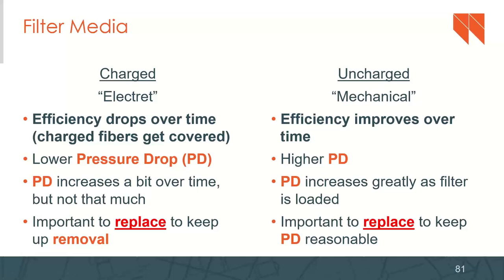With both of these, the pressure drop is going to increase a little bit over time for the charged version, but not as much as the uncharged one. As the filter gets dirtier and dirtier, that pressure drop increases. So it's important to replace and really keep up with the removal of them. For the uncharged one, that pressure drop is really going to increase greatly as the filter gets loaded up.